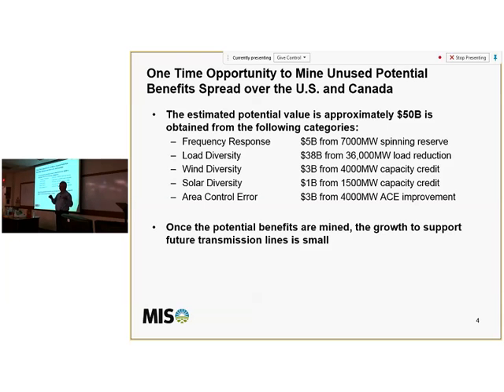Capacity credit translates into deferred or displaced generation, which transmits into money. If you delay a combustion turbine, you're displacing $680,000 worth of investment. By aggregating the wind together with transmission, at least in the eastern connection, you can get the capacity credit for wind to be about 0.25. In Miso right now, it's 0.13, so 13% capacity credit. But if you go to a small system, like when Miso first started, it may be in a range of 2%. So you're getting value out by aggregating transmission.